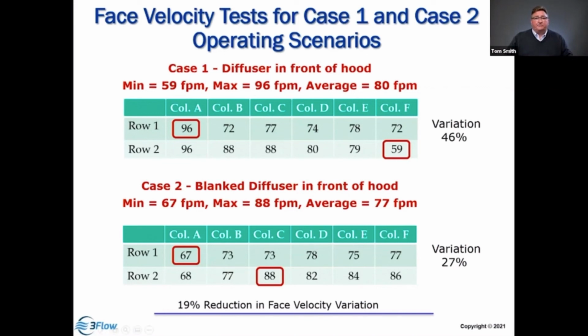Now, two things that we noticed: by blanking off, we had a reduction in the variance of face velocity, which is going to lead to better containment. But we also had a reduction in average face velocity, because in the first case, we not only measured the velocity due to the air sucked into the hood, we're measuring the velocity of the air blowing at the hood as well. And that creates error. It means that we don't know if we're measuring the total velocity or measuring the supply. And so we want to mitigate those cross-drafts to create a more accurate measurement of average. Because what happens if the average velocity is not correct?